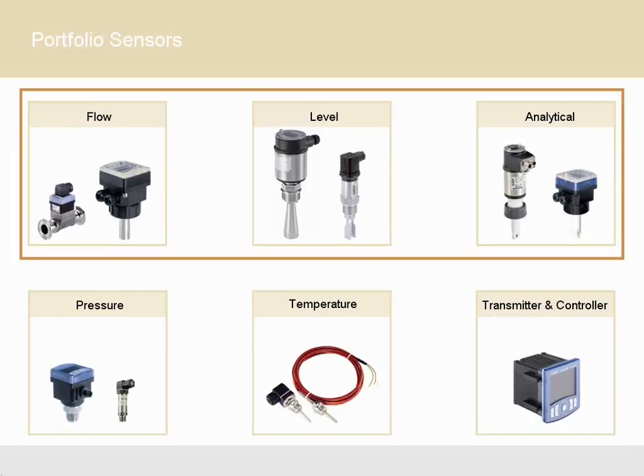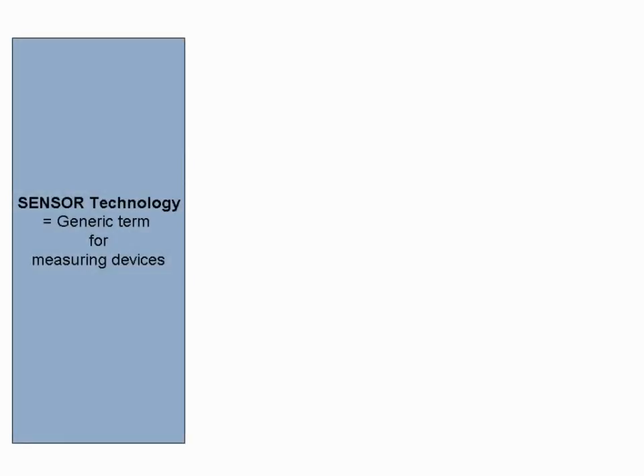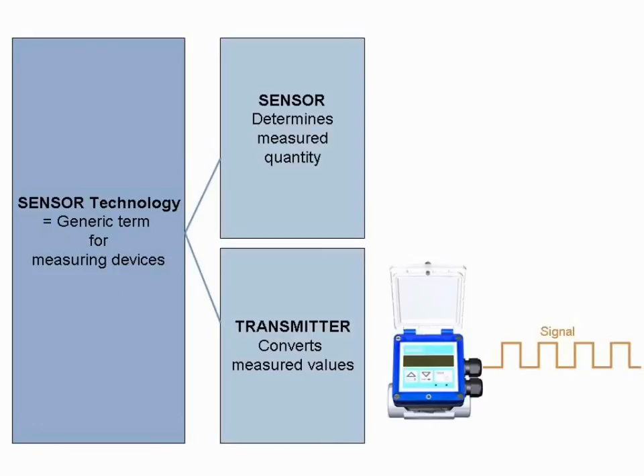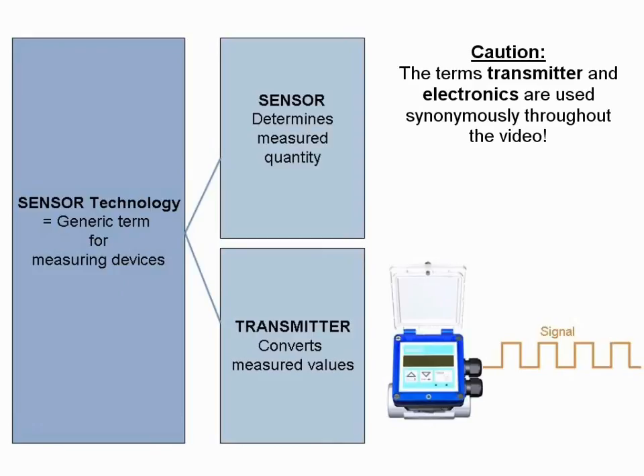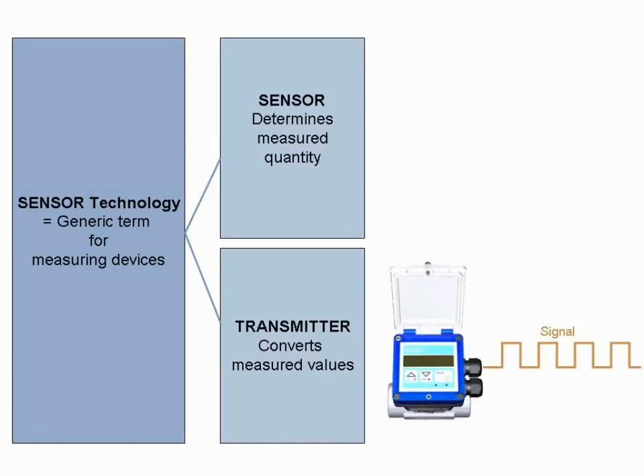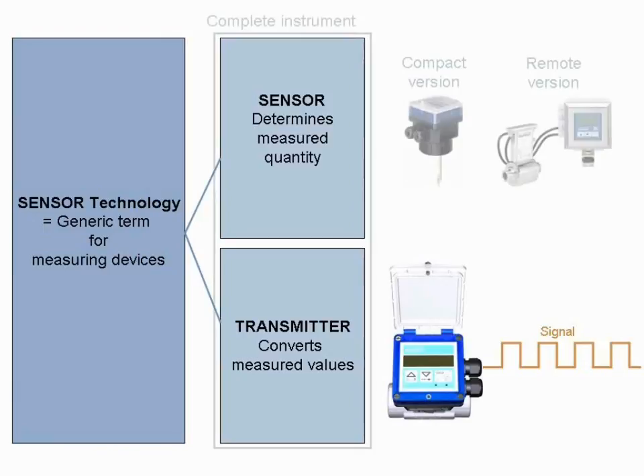Before we embark upon this subject, however, we first have to answer the question, what is sensor technology? Sensor technology is a generic term for measuring devices and can be divided into two primary components, sensors and transmitters. The terms transmitter and electronics are virtually identical in meaning and are used synonymously throughout the video. The sensor determines the measured quantity by means of various physical or chemical processes, and the transmitter converts this measured quantity into measured values, which it presents in the display in the corresponding physical units and outputs as standard electrical signals. The transmitter can be designed as a unit mounted directly on top of the sensor, which is also referred to as a compact version, or as a separate unit called remote version, in which case the transmitter is connected to the sensor by means of a cable.